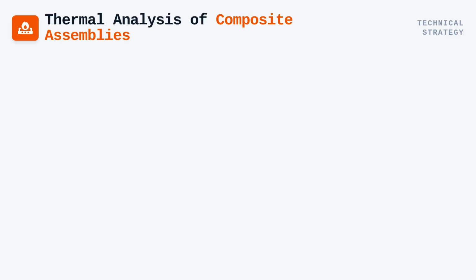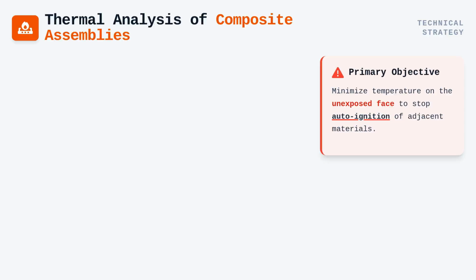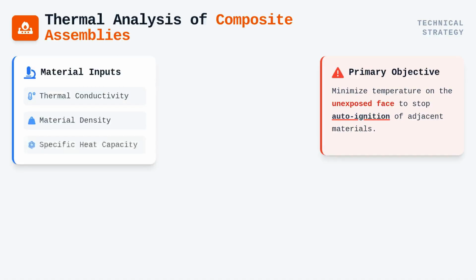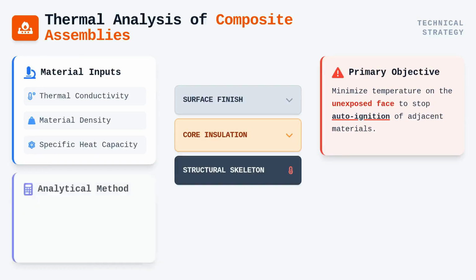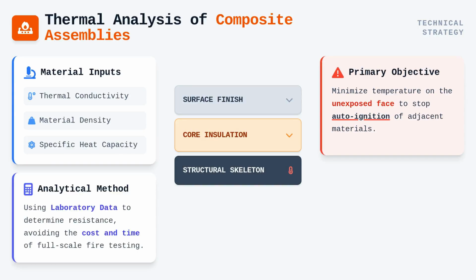When we approach the calculation of heat transfer through composite assemblies, we are essentially performing a thermal analysis of a multi-layered system designed to minimize the temperature rise on the unexposed face to a level that prevents autoignition of adjacent materials. This requires us to look at the thermal conductivity, density, and specific heat capacity of every component within the assembly, from the initial surface finish through the core insulation to the exterior structural skeleton. Analytical methods allow us to determine the resistance of an assembly without requiring the financial and time-consuming burden of full-scale fire testing, provided we have reliable laboratory data for the constituent materials.